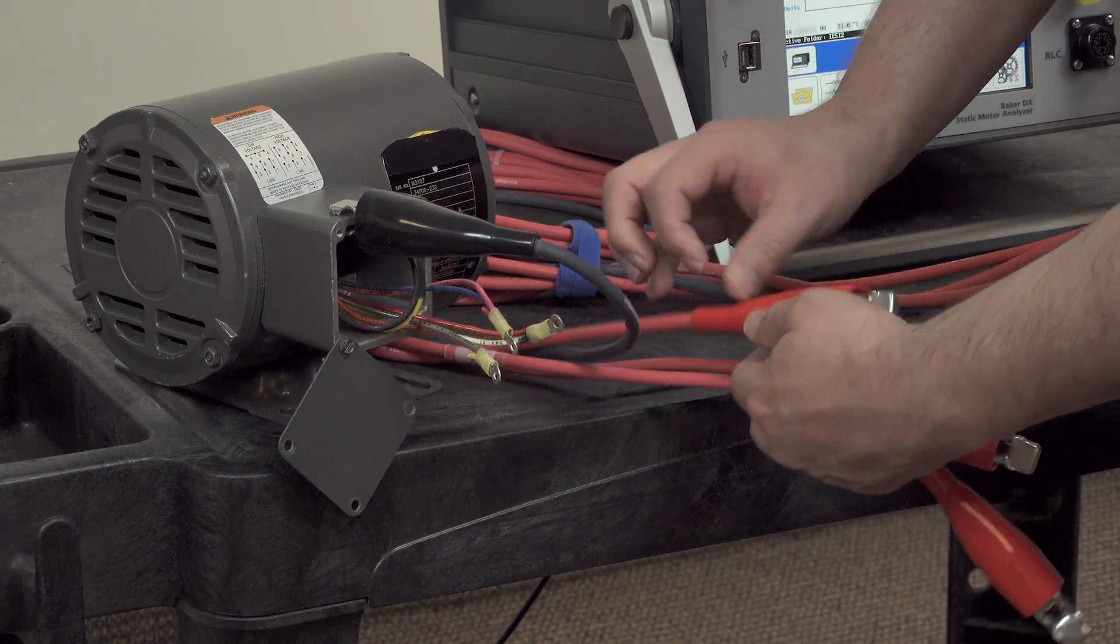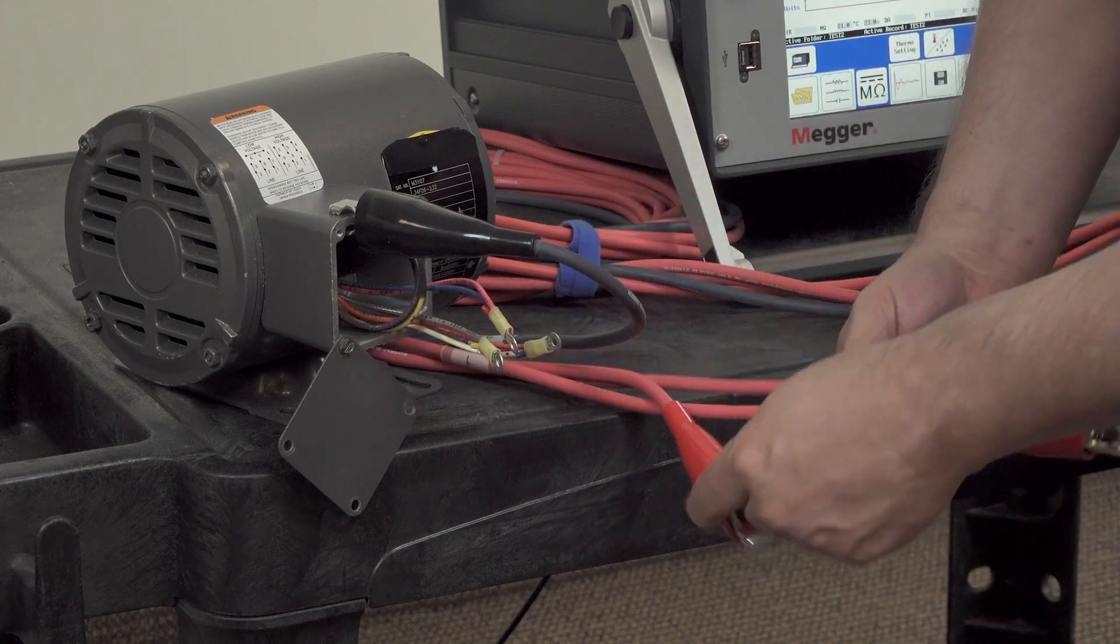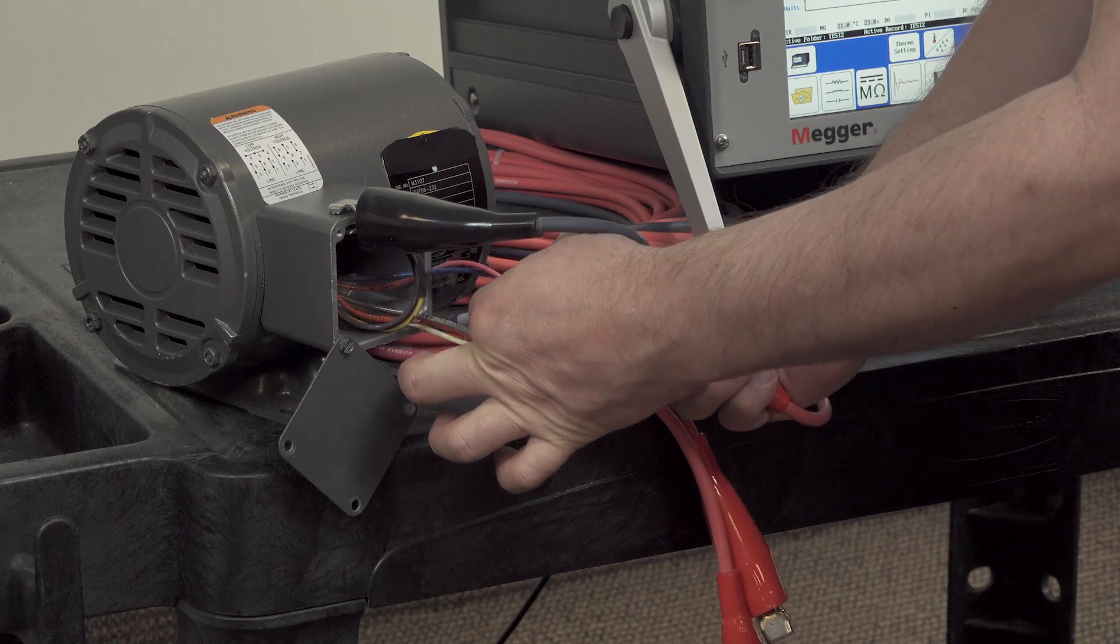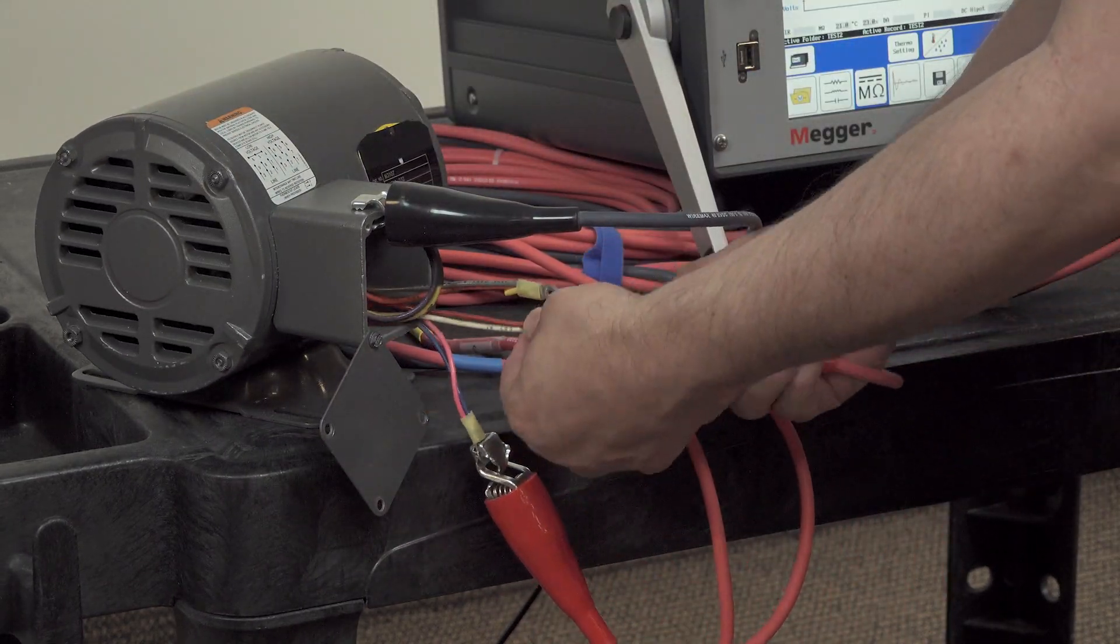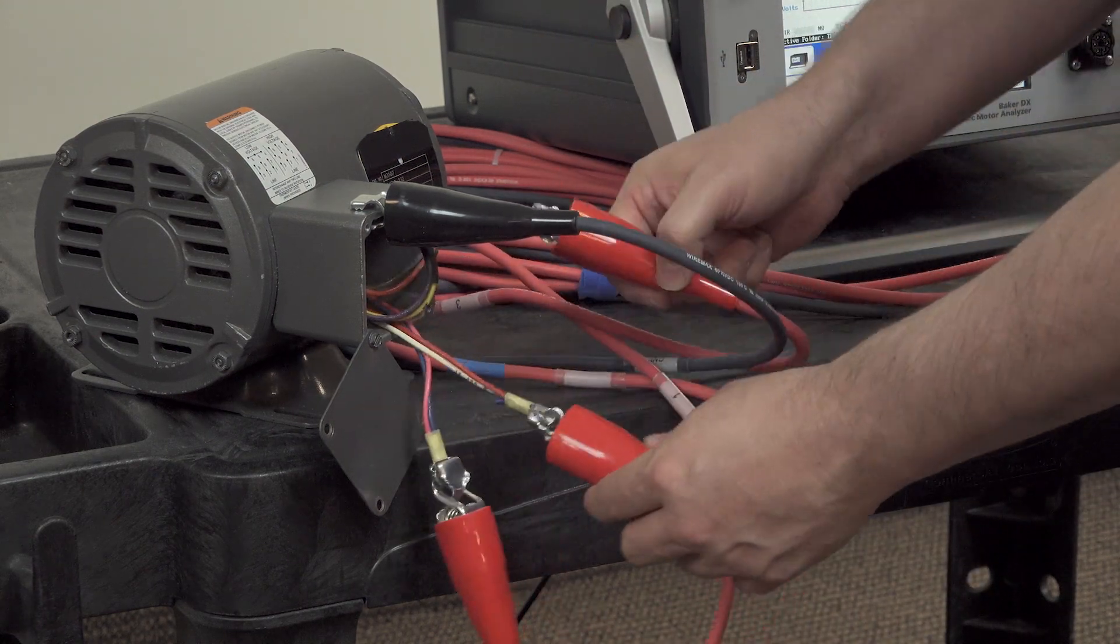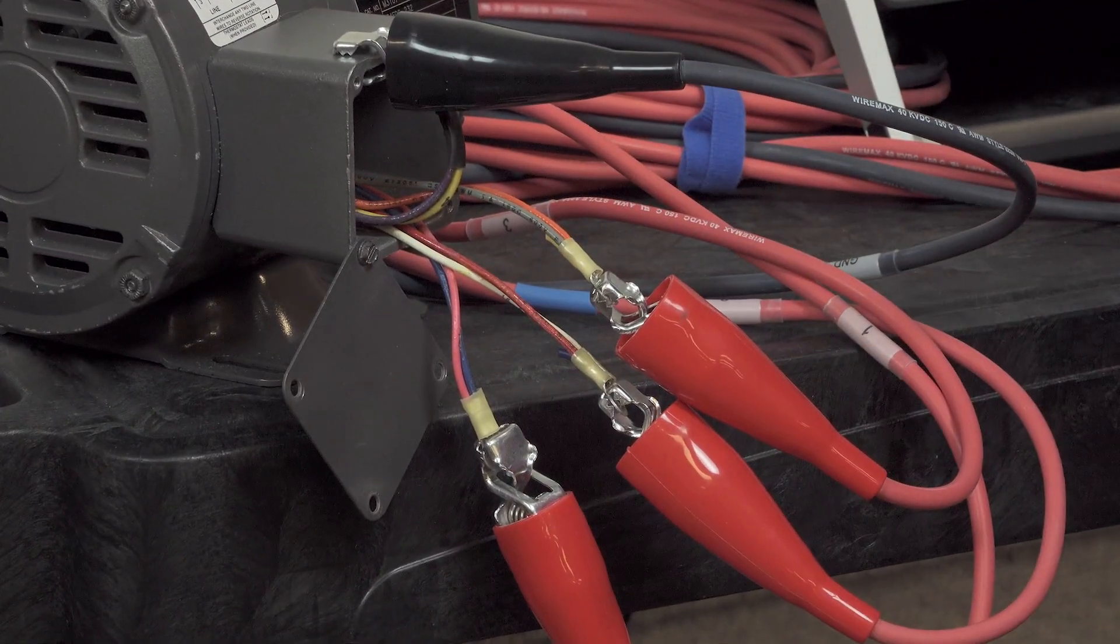Now we'll connect the leads to the motor. We'll connect the ground lead first to the motor frame, and then we have leads one, two, and three. We want to connect them to the appropriate motor leads, ensuring that the leads are not touching and that they're away from any ground sources as well.